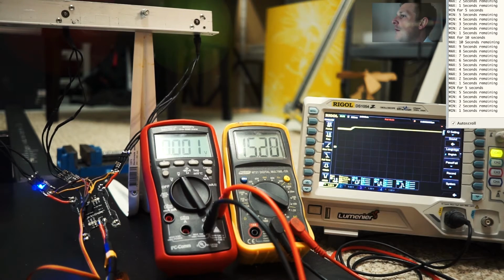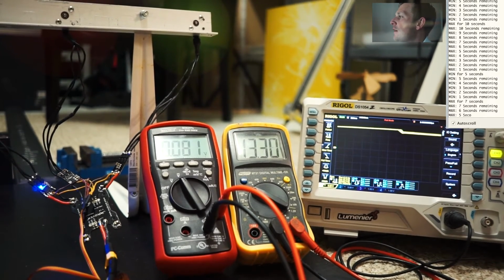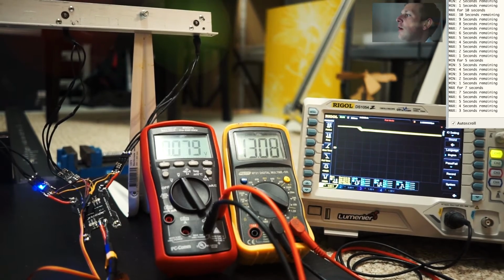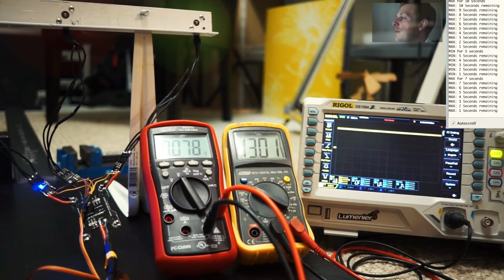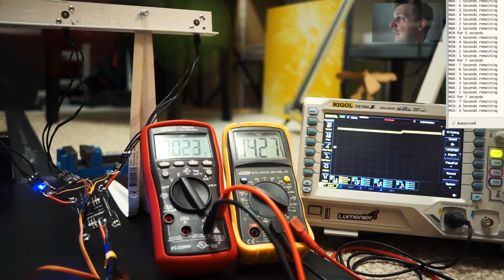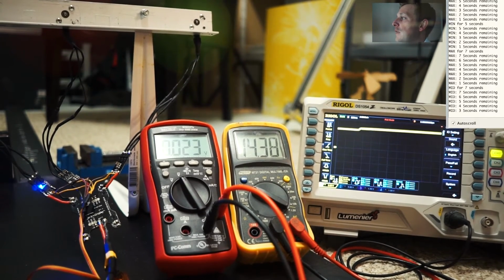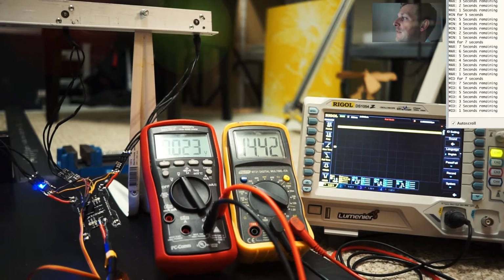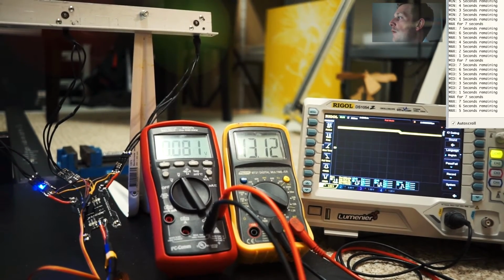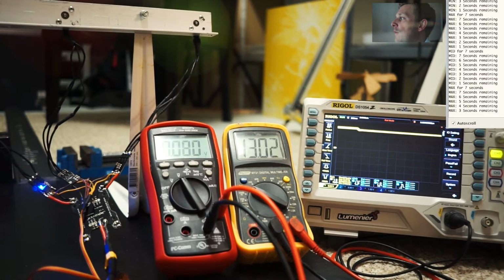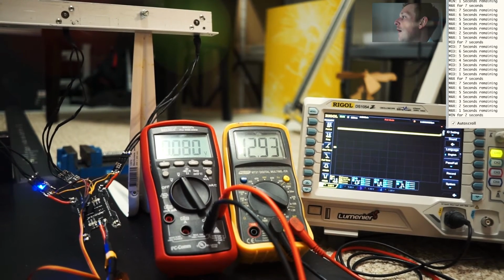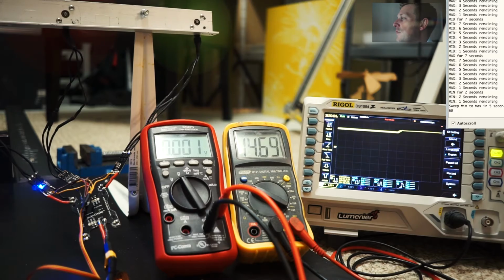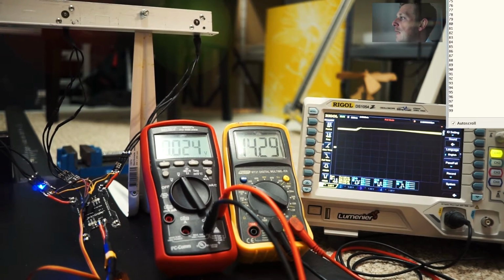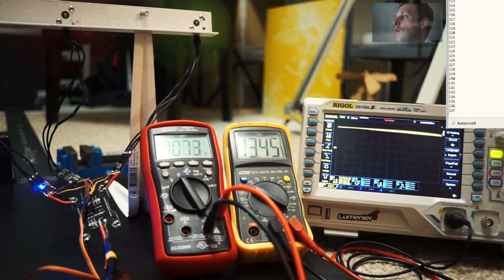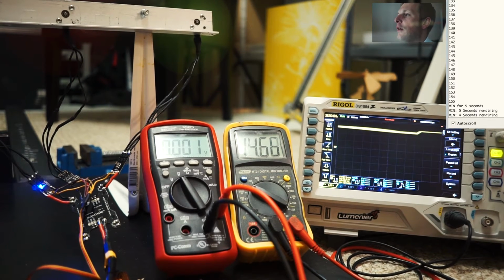Plugging that into the battery testing sheet, it's got a continuous C rating of 40. The actual max coming out of that battery for that sustained period was 76 amps. The lowest voltage was 12.82, so the power delivered was 974 watts maximum. The actual C rating over that period was 54.2, which is quite good because at least they didn't overrate it like most battery manufacturers do.